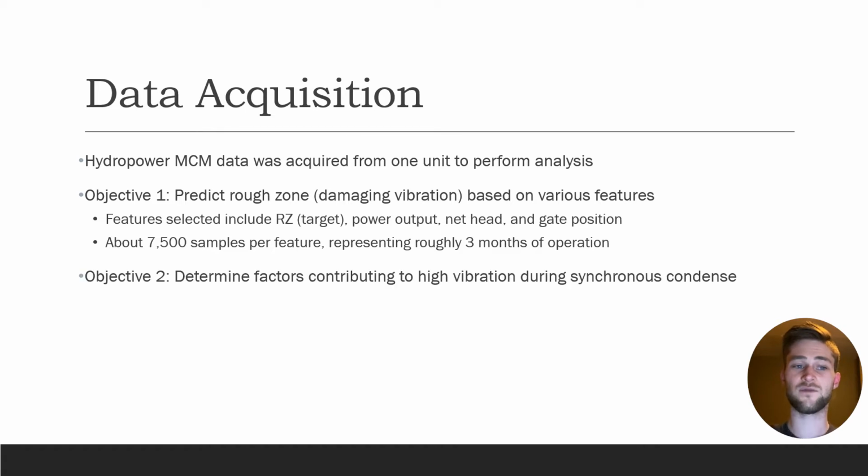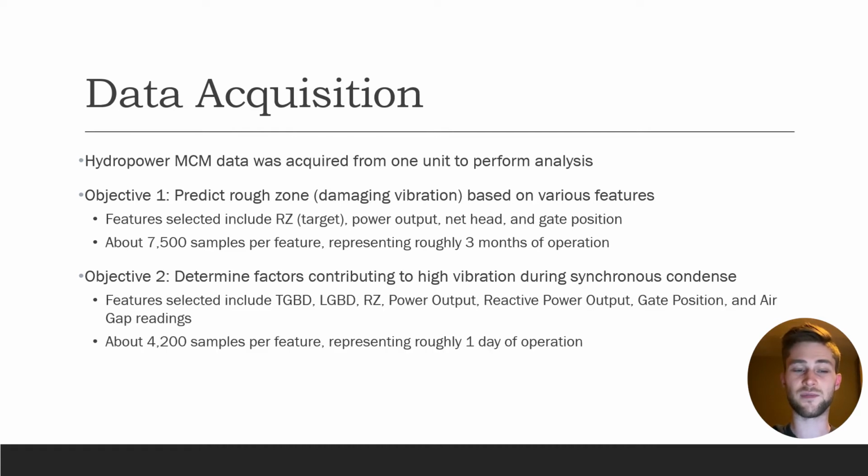The second objective was to determine factors contributing to high vibration during synchronous condense. These features included turbine guide bearing vibration, lower guide bearing vibration, rough zone, power output, reactive power output, gate position, and air gap readings.